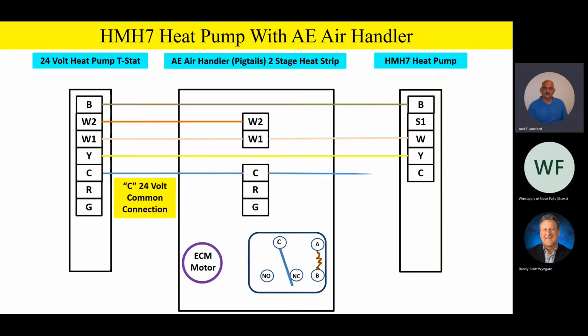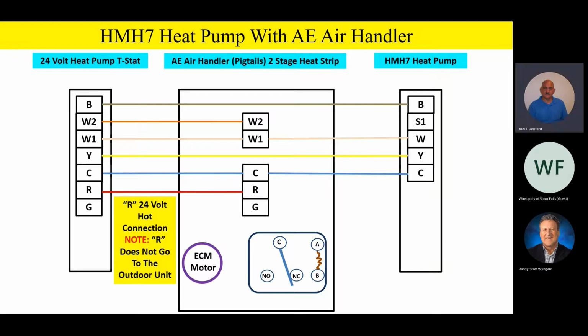Common terminal will go from the thermostat to the indoor unit to the outdoor unit. That's, no pun intended, a pretty common wiring scheme, if you will. R terminal is our 24-volt hot. That will go from the thermostat to the indoor unit. Now, please note something. R terminal does not go outside. So the outdoor unit does not require that 24 volts on the R terminal in order for it to function properly. So the R terminal will not go outside in this product.